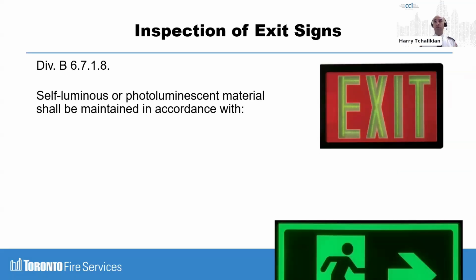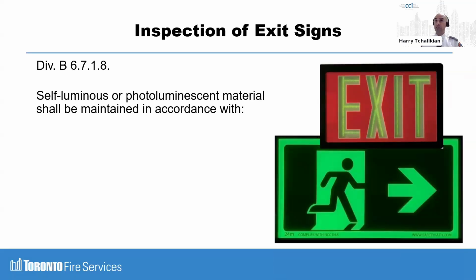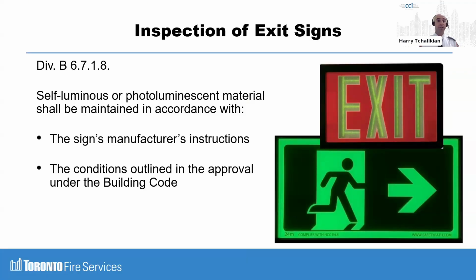Next, self-luminous or photoluminescent material shall be maintained in accordance with the sign's manufacturer's instructions or the conditions outlined in the approval under the building code. These exit signs were always in the building code and they were never addressed in the fire code until now. So not too common. At the bottom one, the photoluminescent, that's your glow in the dark exit signs. And the top one, that's your self-luminous, which is not as common.